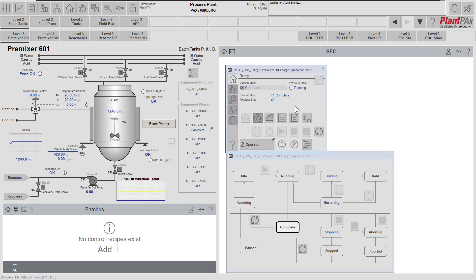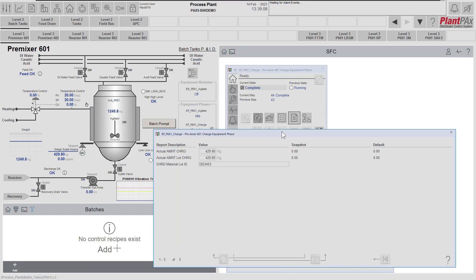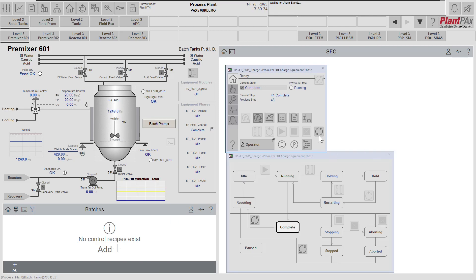As our equipment phase is now complete, it has reported some values as part of the implementation sequence in our process controller. Looking at the report values, we can see that the actual amount charged was 429 — including the overshoot. The lot of material charged is again 429, there was just one lot of water added, so the lot weight matches that same amount, and the material ID of that lot has also been recorded. Let's now reset our phase back to idle so it can be used again to perform another charge.